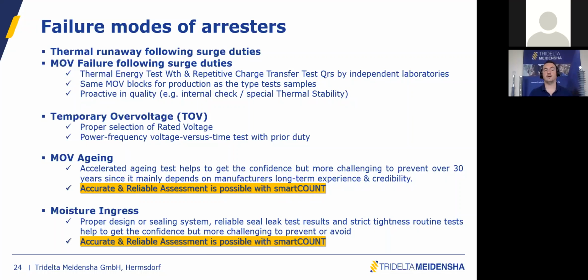But there are two types of failures which are pretty common and that can be assessed by using a monitoring solution. And this is exactly the reason why we developed this state-of-the-art solution. Philip will give you more details about MOV aging, how to assess MOV aging, and how to assess moisture ingress on the surge arresters. It's a very common question when you have an old substation with surge arresters more than 30 years old: how can you have the confidence that those surge arresters are still in good condition and that they protect your equipment? I think that's the main question.